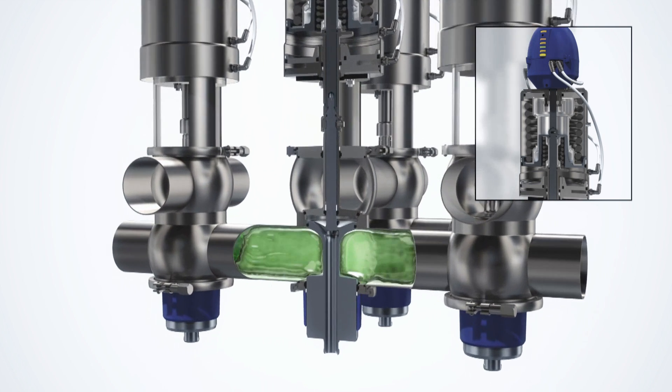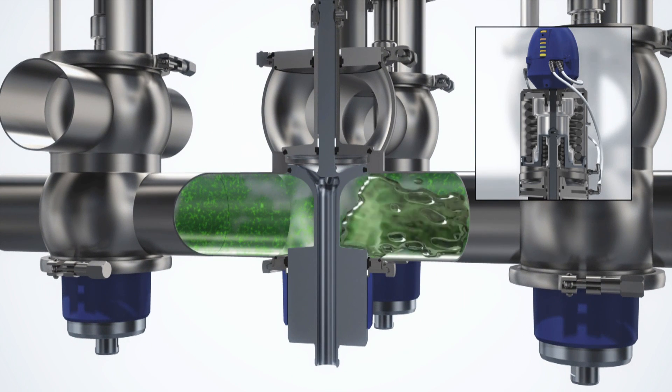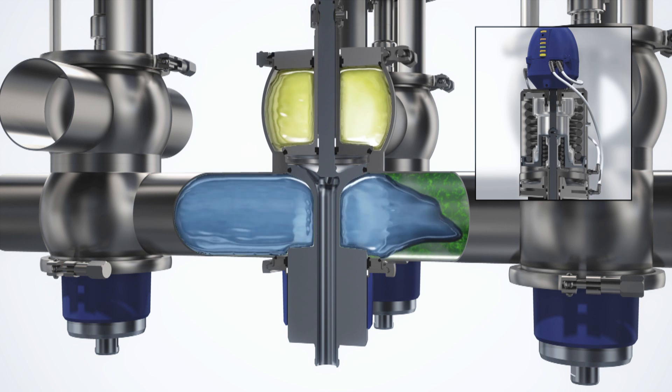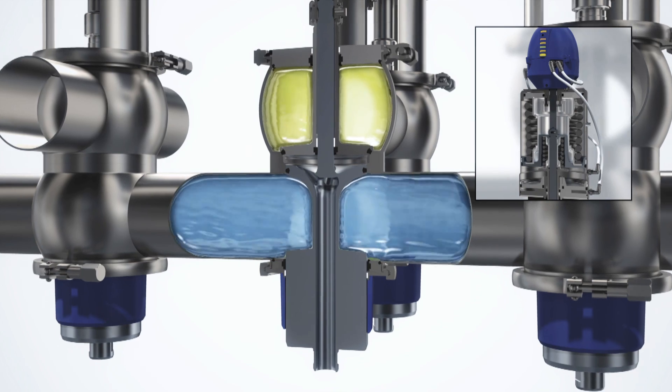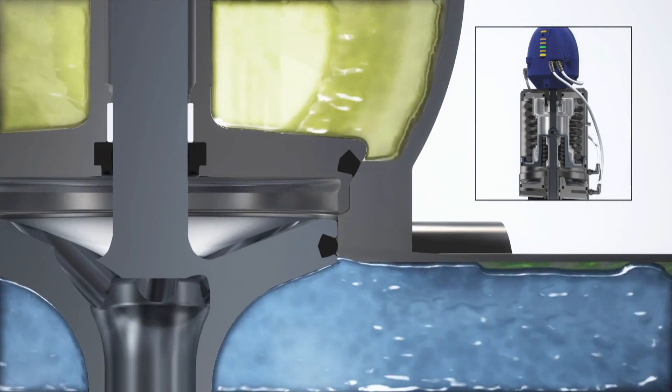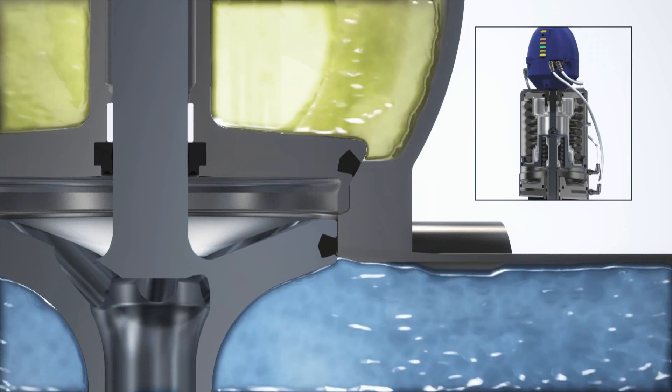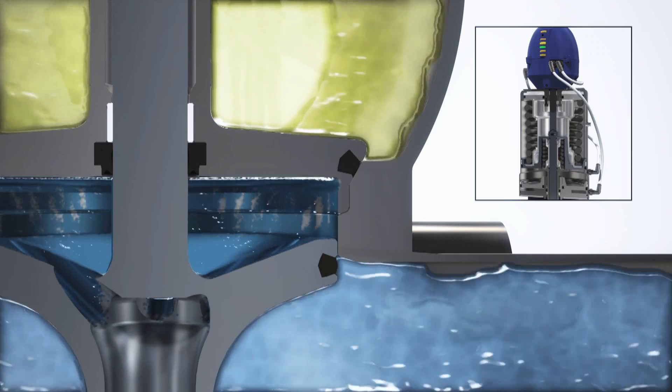The design of unique mix-proof valves enables different products to flow through each section of the valve bodies without any risk of cross-contamination. Like the seat lift operation, the fast-acting seat push function is controlled by a defined metal-to-metal opening, which provides a throttling edge.